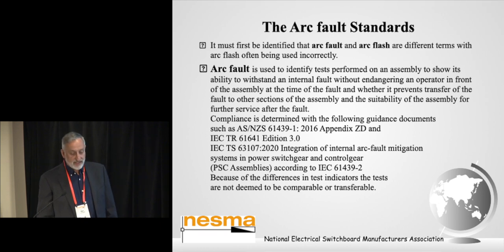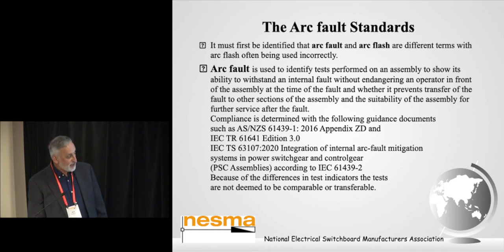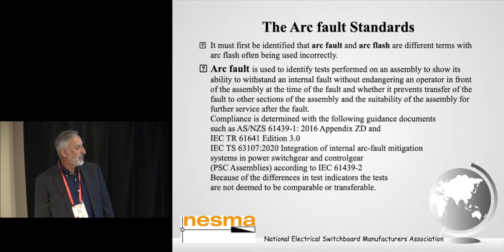There is another standard that has been developed by IEC, which is the 63107 2020, which is the integration of internal arc fault mitigation systems in power switchgear and controlgear, PSC assemblies according to Part 2. And because of the differences in test indicators, the test to ZD compared to IEC TR 61641 are not deemed to be comparable or transferable.